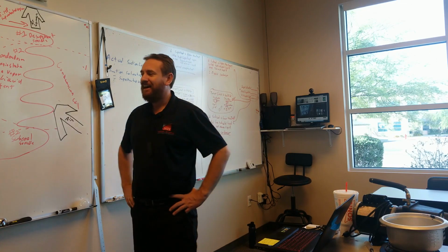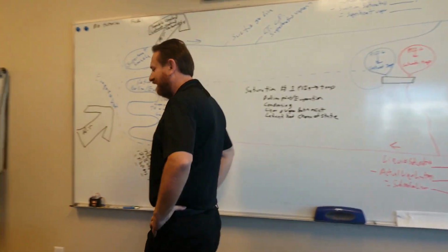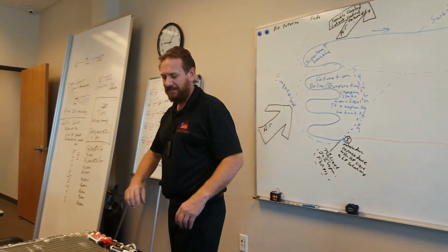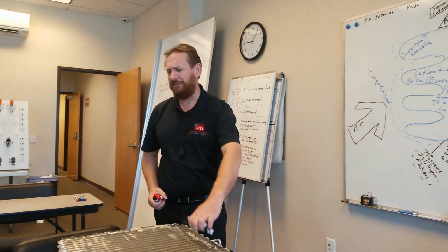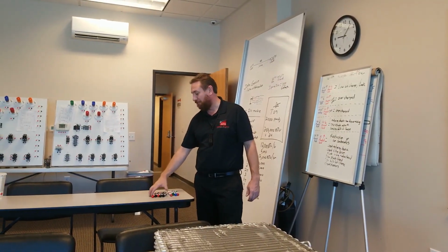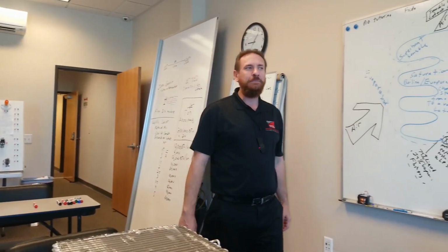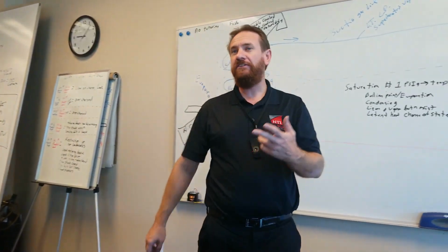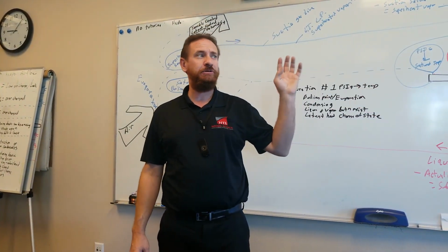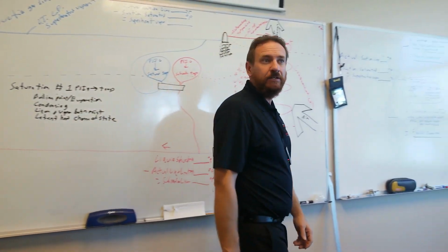So, yes, we do size units. We size them with a heat load calculation. Square foot per ton, stay away from that. Now, if somebody says square foot, don't call them dumb, all right? I'm not saying that. But in your mind, you need to be going, square foot per ton proves you're dumb. A lot of people just got hung up on either the old school way of doing it, not actually wanting to appreciate it, or doing a heat load calculation is too complicated.